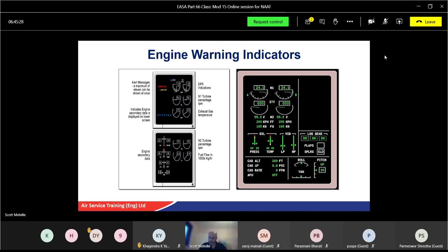If we disconnect a temperature indicator gauge, what will it read? Local ambient temperature specific to that day. What is the T1 thermocouple normally made from? Iron and constantan. Good.